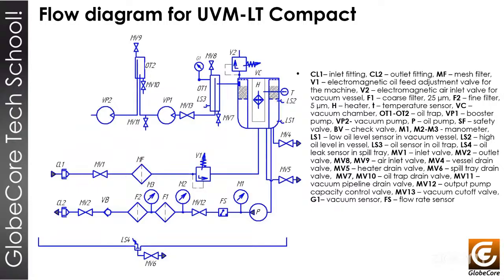Now this is the diagram of the UVM-LT Compact unit, and you can see here the inlet connection, the inlet valve, the inlet filter, the mesh filter, which is the big filter in the machine. We have an automatic valve. This will depend on whether the level is really high here. LS2 is a level sensor that will close this valve to avoid the oil continuing to go up inside the machine. Then the oil will continue this way and will find the heater. The heater will be full of oil, and when it reaches the top of the heater, the oil will come through this special cover and from the top to the bottom.